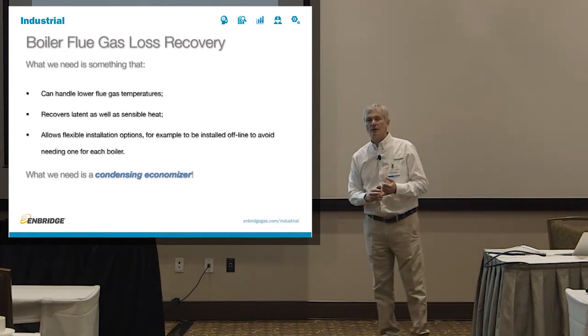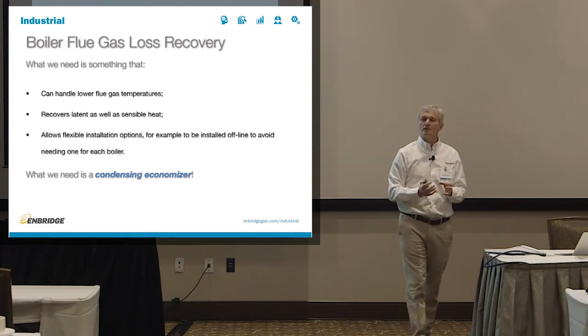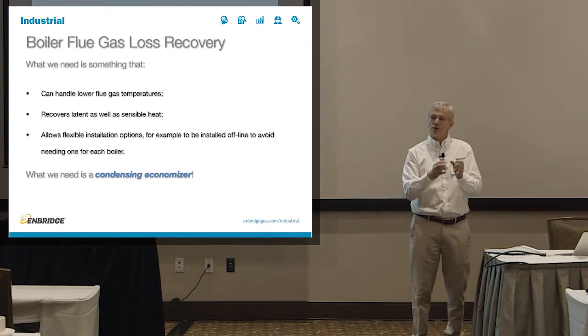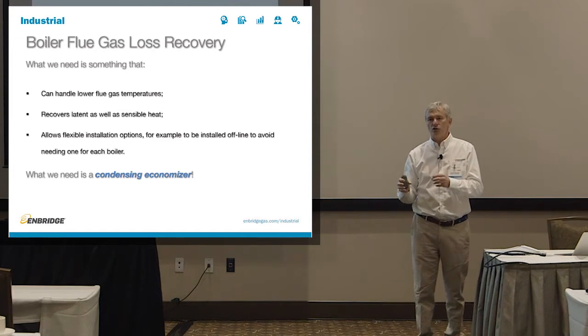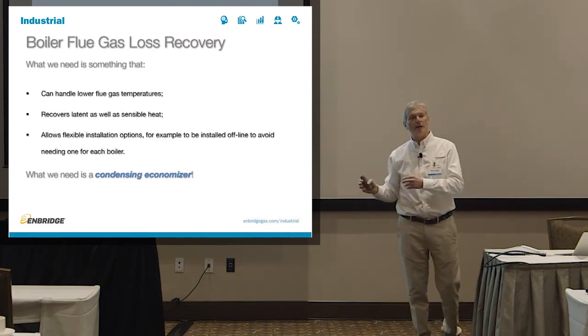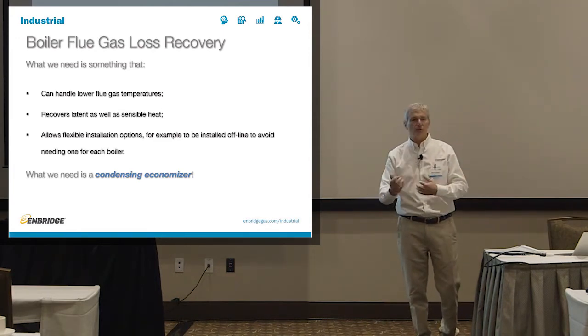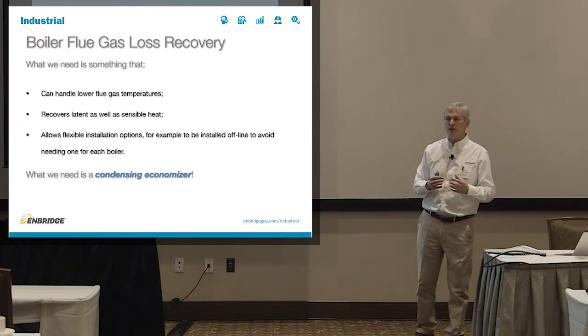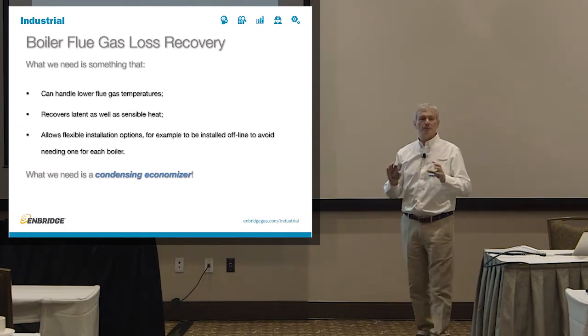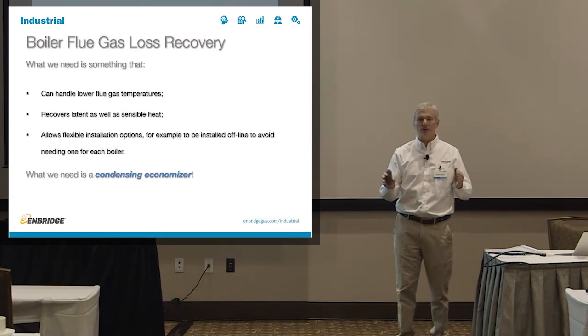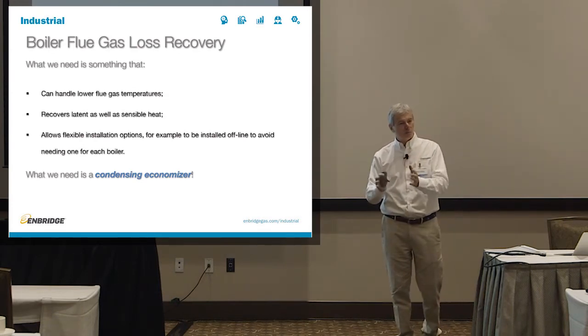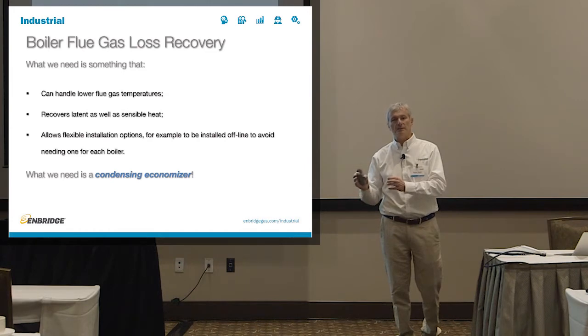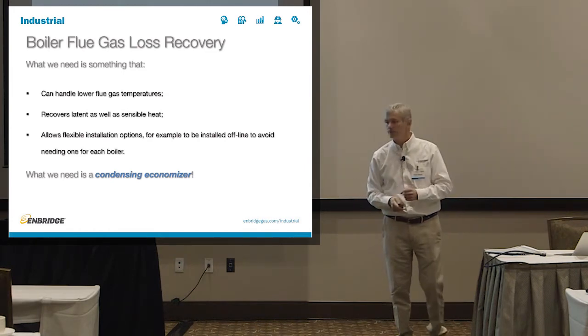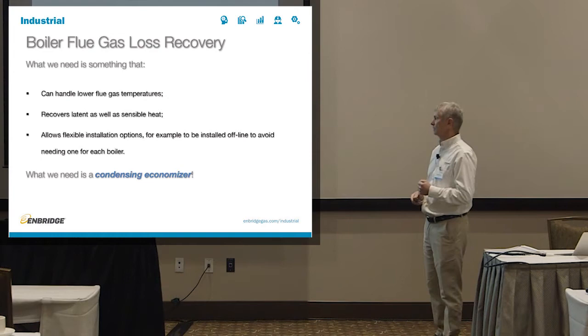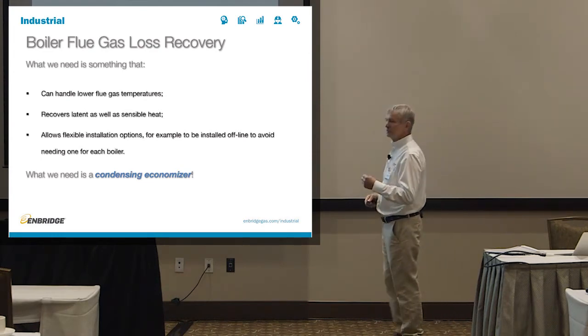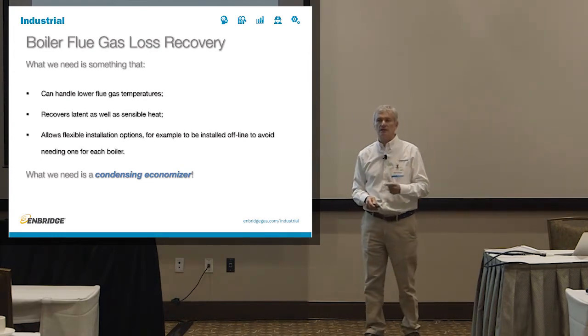And it would be nice to have flexible installation options. Feed water economizers are inexpensive, but you have to put one on each boiler. It's a very rare application where you can put a feed water economizer offline. So you can feed, let's say, three boilers with one feed water economizer. That usually doesn't work that way. So it would be nice if you can have something you can put offline and you have a three boiler system. Whenever you switch the boiler, the boiler that is currently working is using the same heat energy recovery mechanism as the other one, without the investment of three separate ones. So what we really need, what we really talk about here is a condensing economizer.